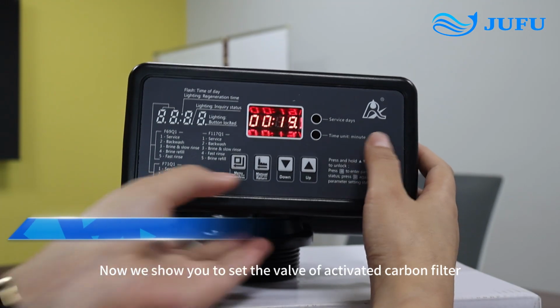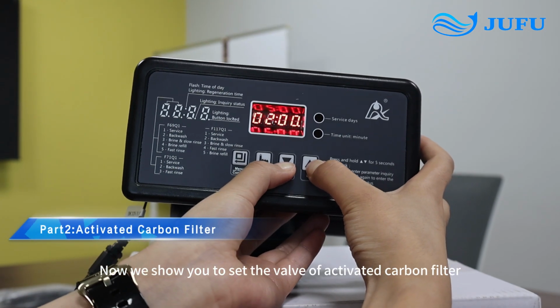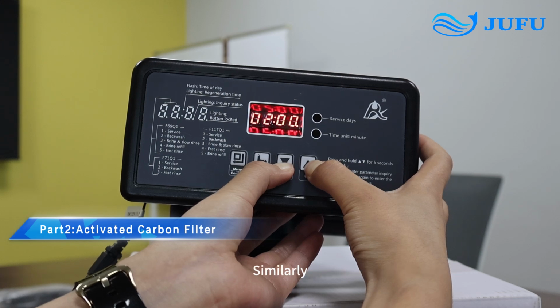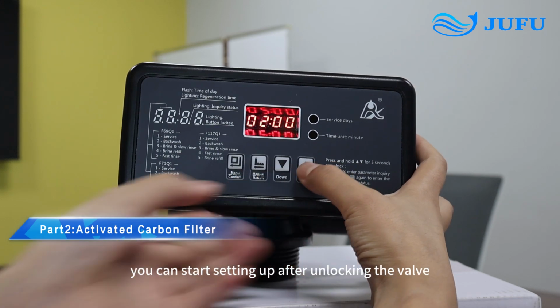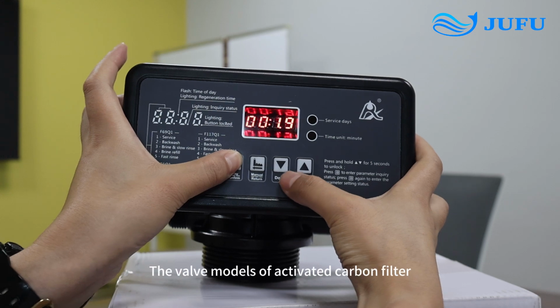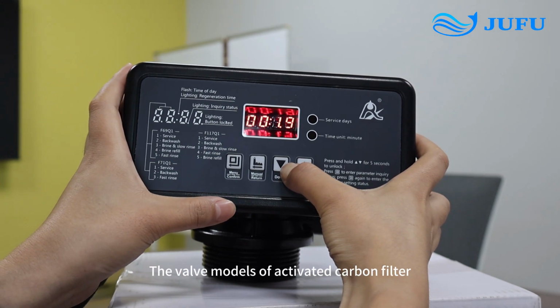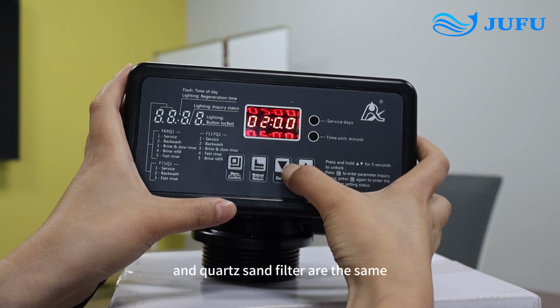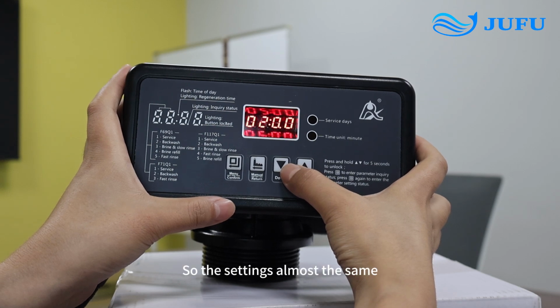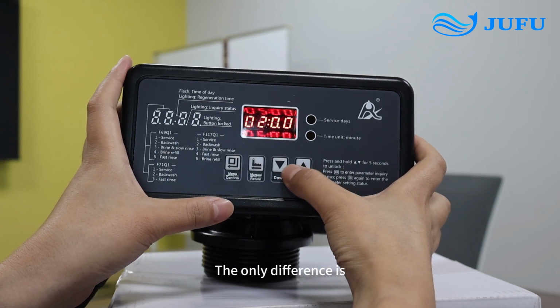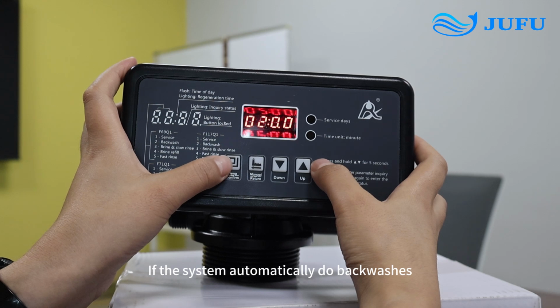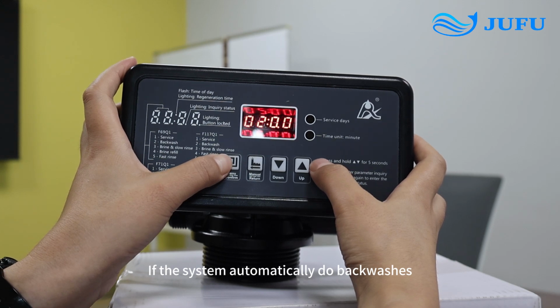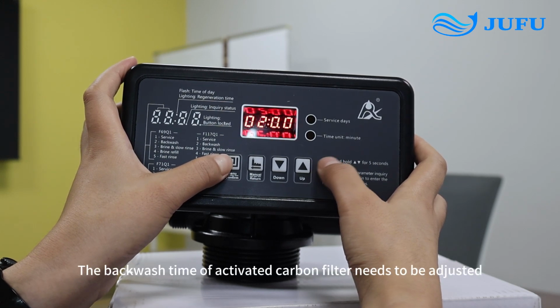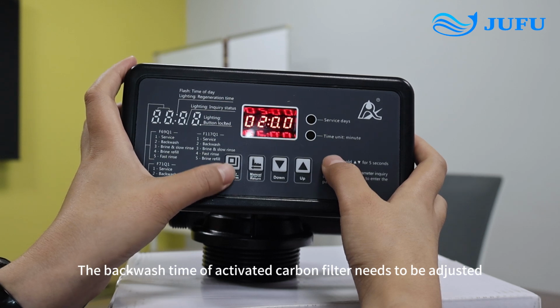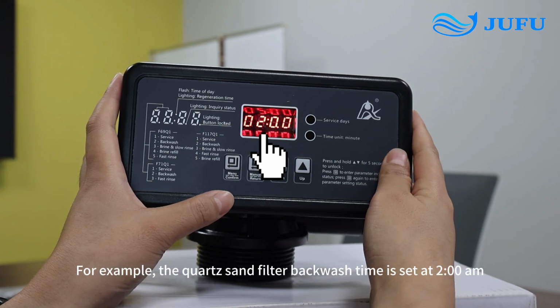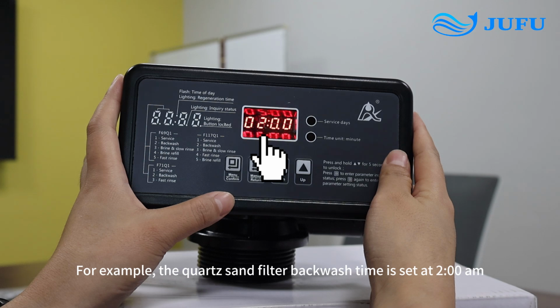Now we show you how to set the valve of activated carbon filter. Similarly, you can start setting up after unlocking the valve. The valve models of activated carbon filter and the quartz sand filter are the same, so the settings are almost the same. The only difference is, if the system automatically does backwashes, the backwash time of activated carbon filter needs to be adjusted. For example, the quartz sand filter backwash time is set at 2 a.m.